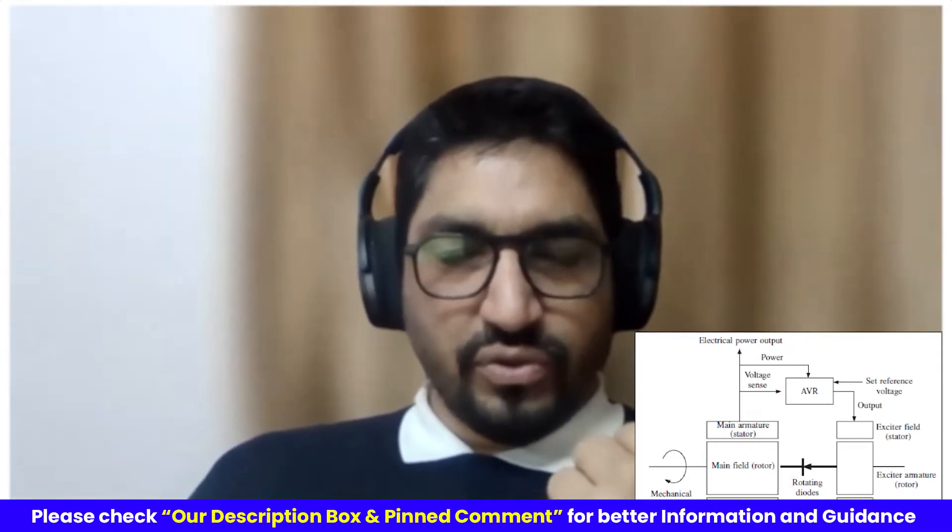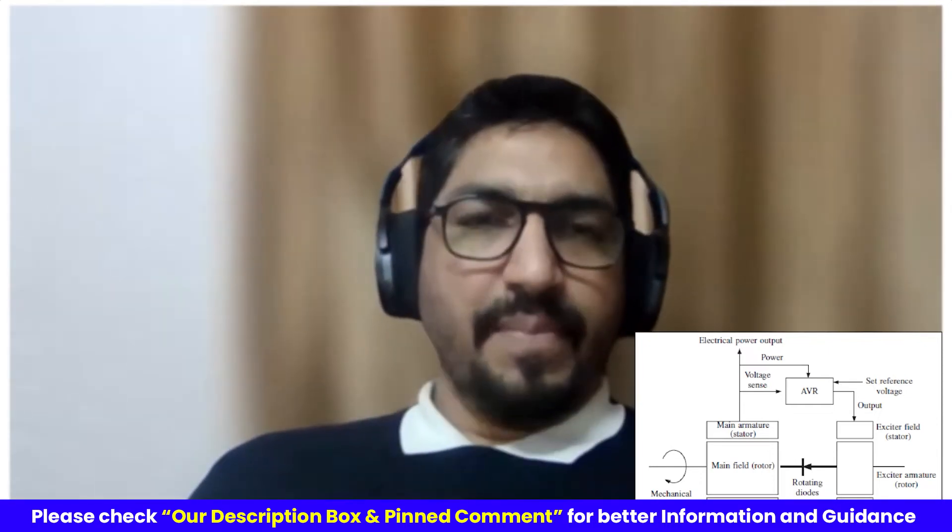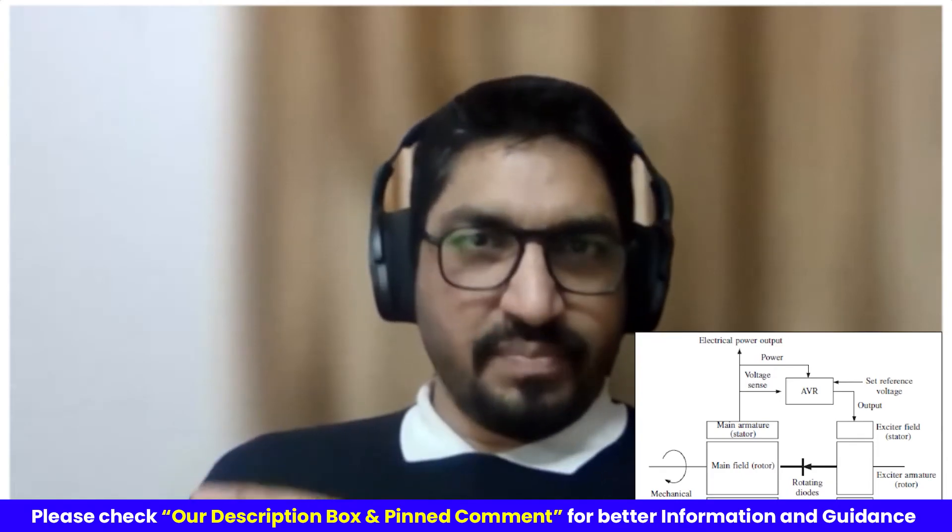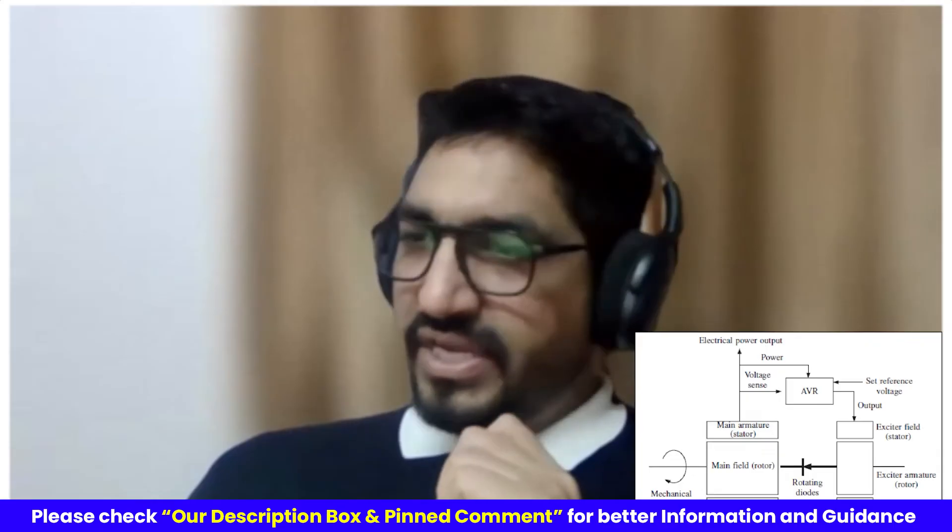Based on this DC power, or DC current value, that exciter is controlling the DC to the main rotor, main section, main generator. And this DC will further control the output. This is how the chain reaction will happen.